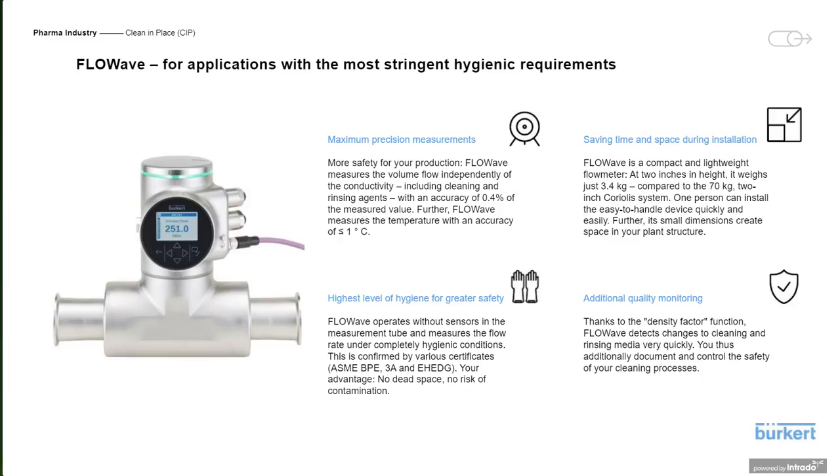Regardless of the conductivity of the fluid, FLOWave can be used in both conductive and non-conductive situations. I noticed a question here about air bubbles. Hendrik, correct me if I'm wrong, but FLOWave can handle up to around a 40% cutoff of entrapped air or bubbles. So I think when you look at a pharmaceutical application, FLOWave would be more than suited to handle the applications that we've talked about and many more.